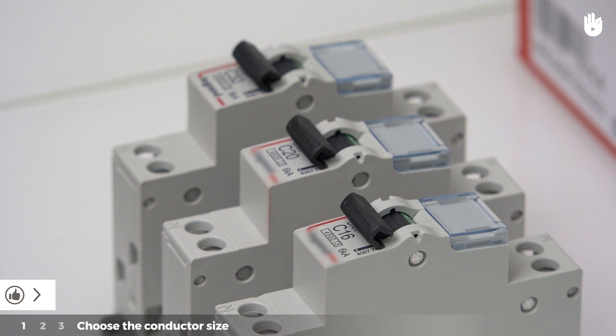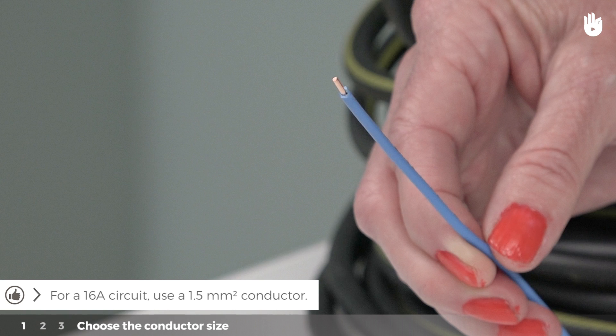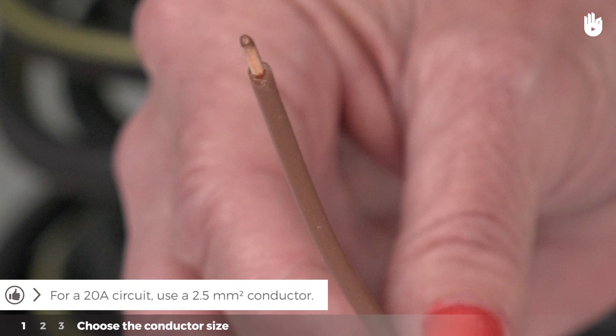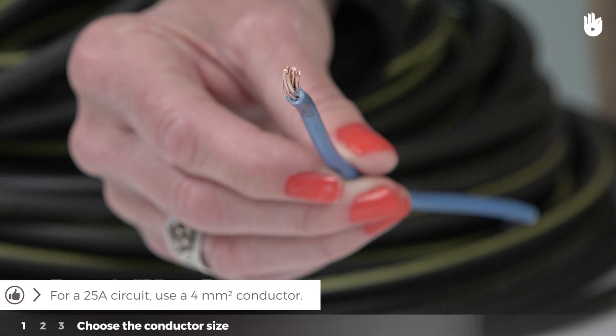If the maximum load allowed in the circuit is 16 amperes, a 1.5 mm squared conductor size will be adequate. For 20 amperes, choose a conductor with a cross-section of 2.5 mm squared. For 25 amperes, a 4 mm squared conductor.